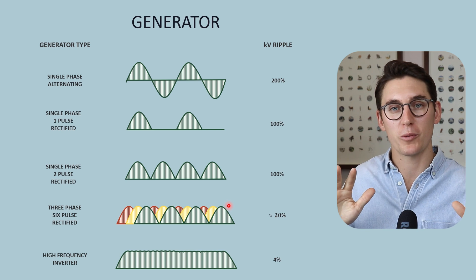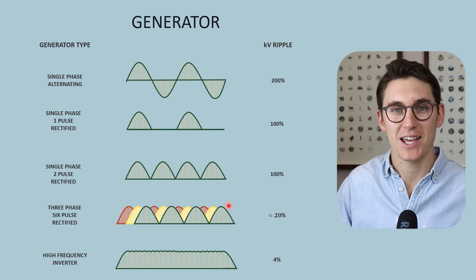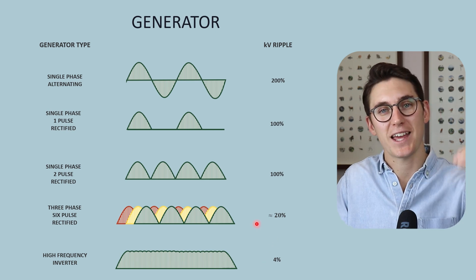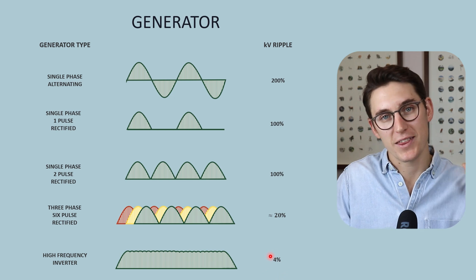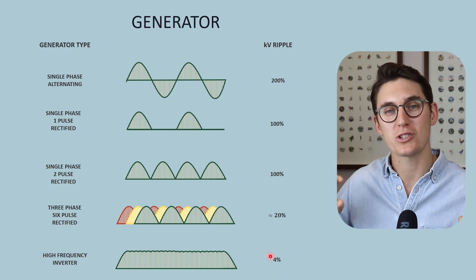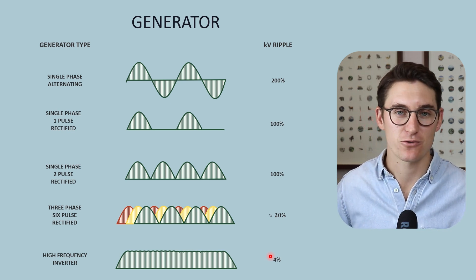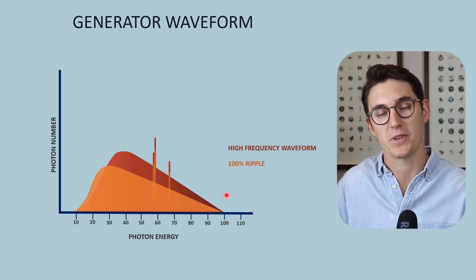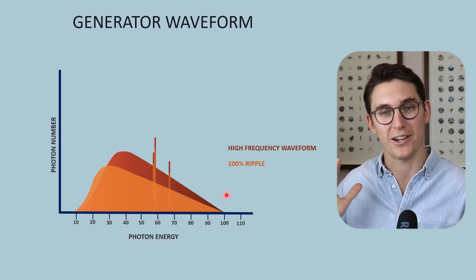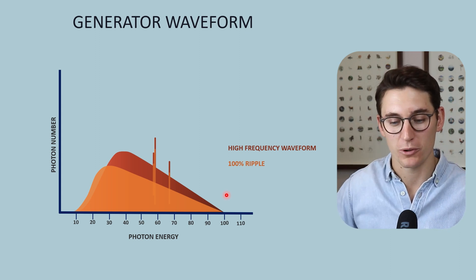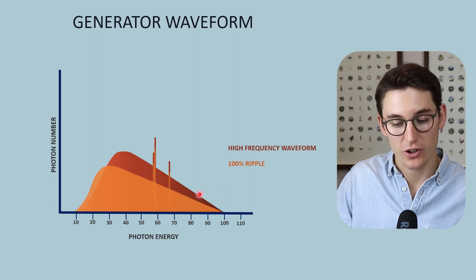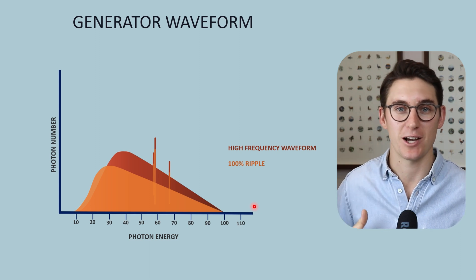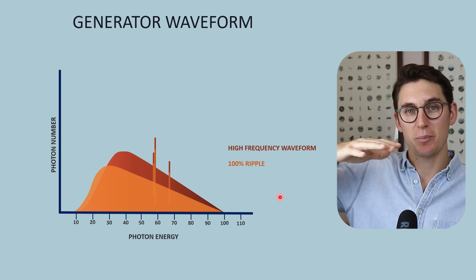When we overlap those ripples more or use a high frequency inverter, we reduce that KV ripple — reducing the difference between our KVP and our lowest kilovolt. A high frequency waveform provides a more direct flow of electrons from cathode to anode at a set energy level with very little ripple between maximum and minimum KV. This gives us a lot of photons being produced — a high x-ray beam quantity. When we use a higher frequency waveform, our KVP remains higher for longer.